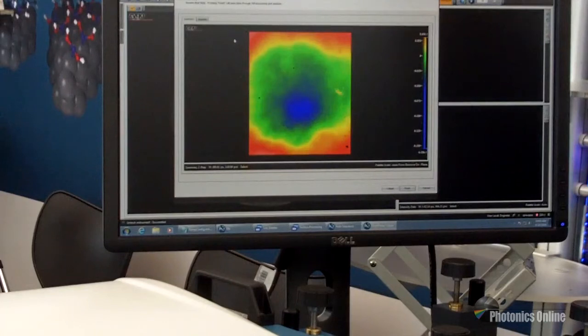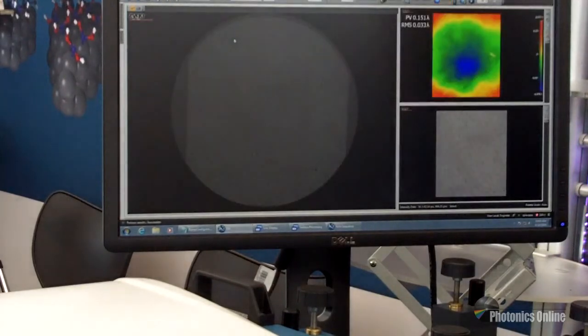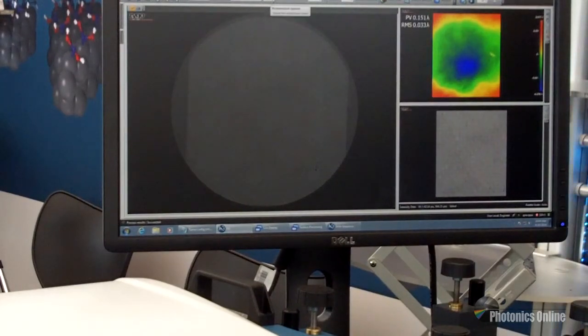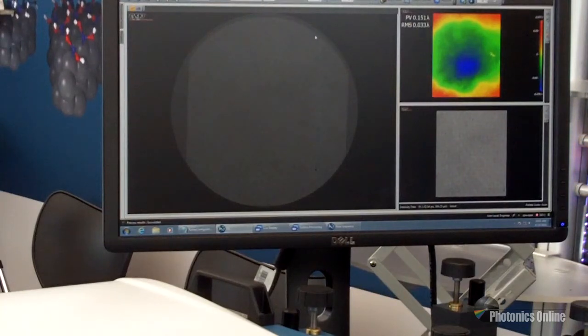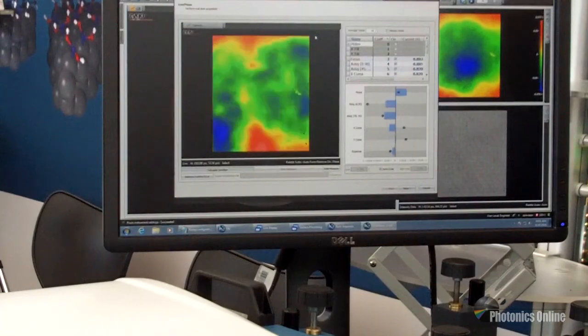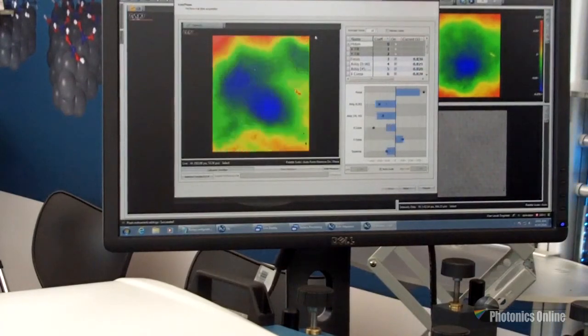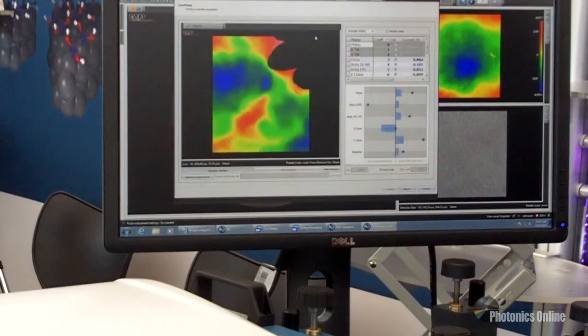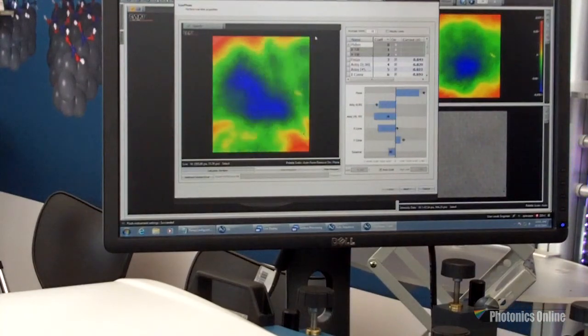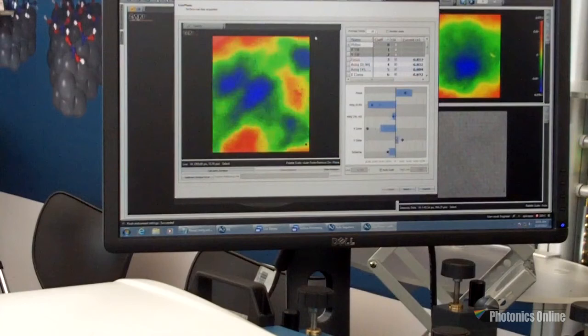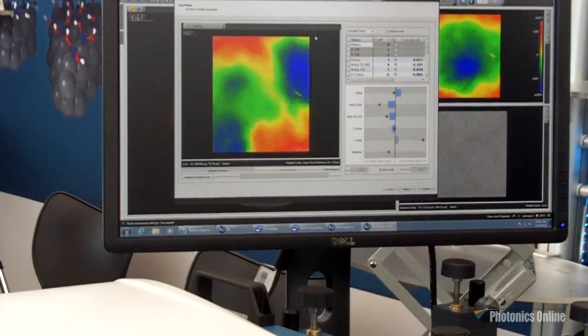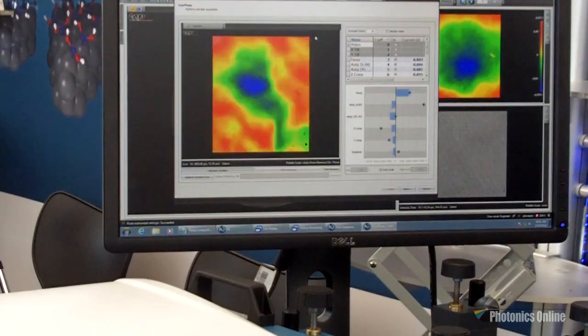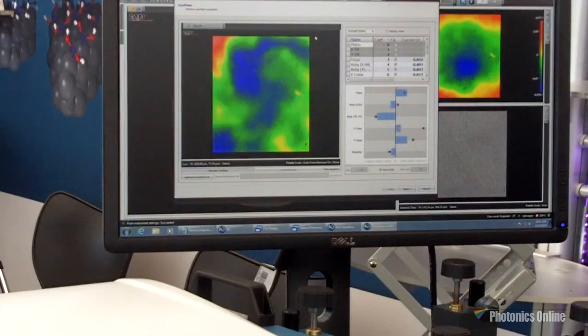If I'm satisfied with the calibration, I now have a final map of the surface. I can continue to make measurements of that surface. I can do that in a live mode. Here I've just activated taking interactive measurements. You'll see now, we've got significant turbulence. Again, that could be through a series of averages, effectively mitigated for final metrology.